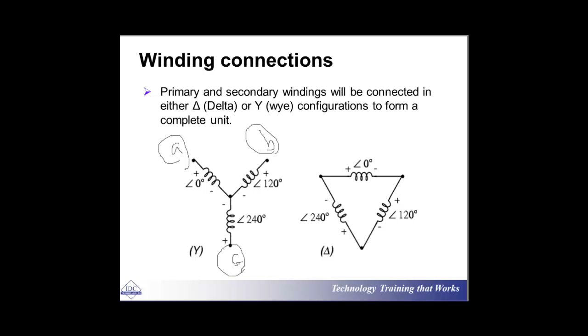As a result of these, you will have some phase shift between the two windings of the transformer. That phase shift is given to you on the nameplate of the transformer as the vector group, and that has to do with the design of the transformer.